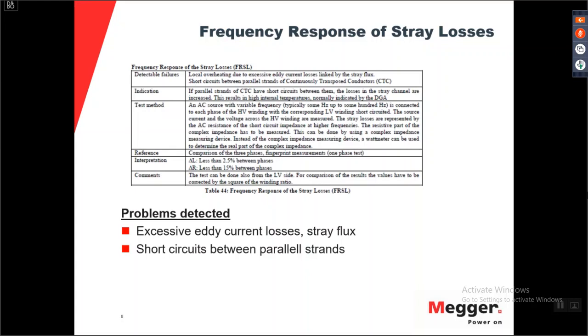So with this, we will find local overheatings due to eddy current losses and stray flux, or short circuits between parallel strands. Not all know what a parallel strand is, so I have some pictures coming later on where I will try to explain it in a better way. So even if you don't know it, bear with me, I will try to do this. The indication for this type of fault is usually a DGA, a high temperature fault.